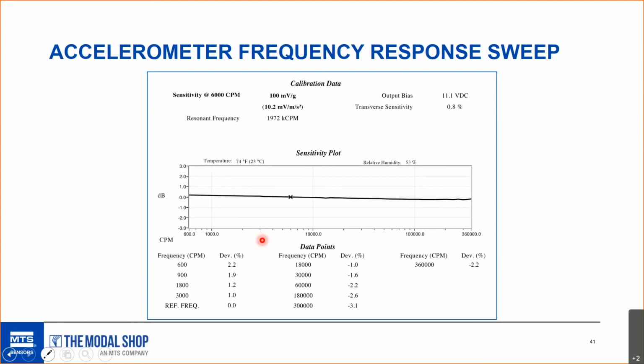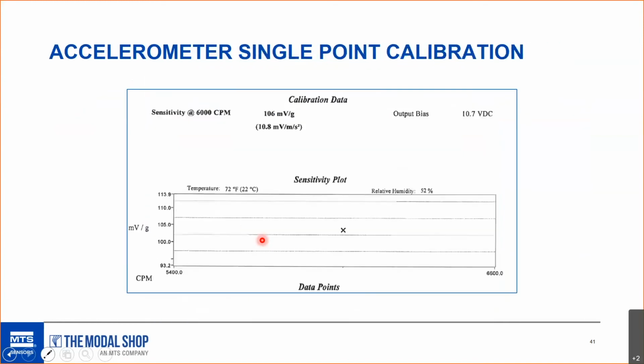So it's very important that you do the sweep, and all of PCB's precision industrial vibration sensors come with a full frequency response sweep. And then this is a single point calibration. This is not recommended per the ISO 16063 Part 21 standard, but you do see it in the industrial market on lower cost accelerometers. And just like anything else, you get what you pay for in vibration instrumentation as well. There are a lot of companies that'll just offer a single point calibration and a very low price for their transducers. The downside is we do not know if the sensor is accurate at other frequencies besides 6,000 CPM or 100 hertz. So we have no idea.